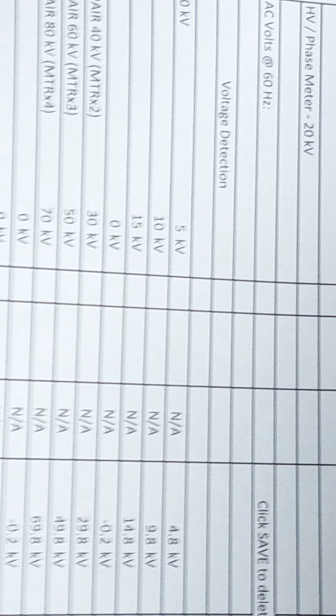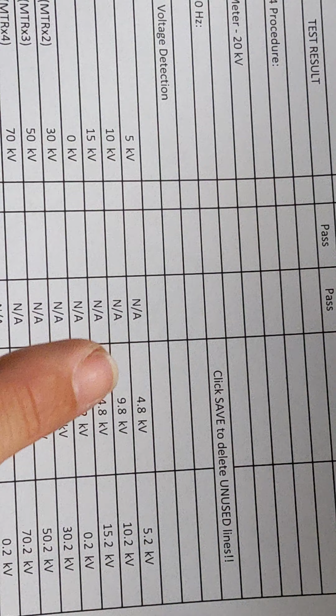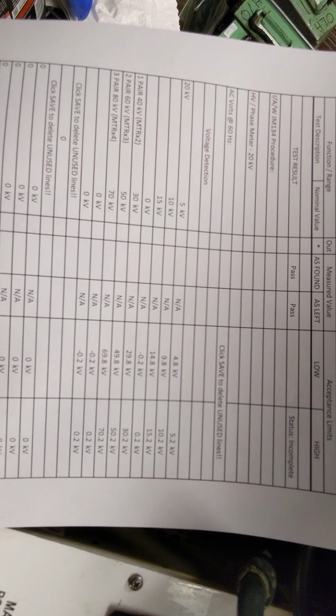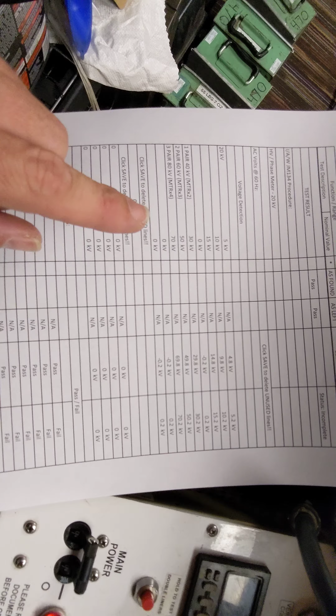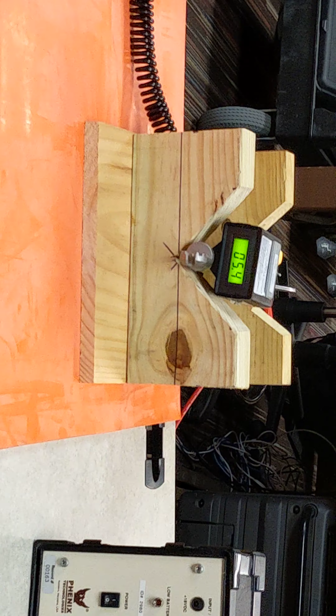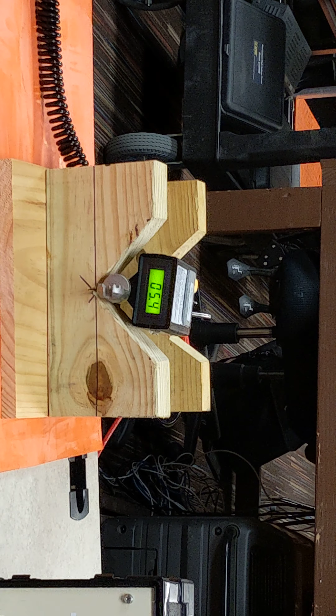So we'll go back to our console. We're at 4.26 and increase to right about 5. It's going to be difficult to get exactly 5, so you can do the math as well. If you're sitting at 5.3 here and you're at 5.4 here, well, then you can just deduct 0.3 from here and 0.3 from here, and that should put you at 5.1 for your phasing meter. So with a known voltage of 5.3 read by our standards, we're looking at 5.1 measured by our customer's piece. So going back to our data sheet, we're in tolerance at 5 kV because we're reading below 5.2 and above 4.8. So that test parameter is passing.